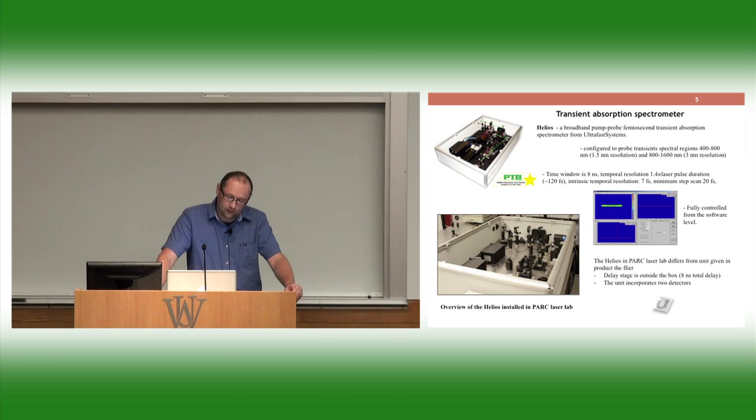If you'd like to measure some processes that take in time scale like 20, 50, 100 femtoseconds, it would be impossible to resolve from another component. It would be just buried under the instrument response function. However, the intrinsic temporal resolution is very good. If we do some upgrade in the future and we have like 15-20 femtosecond laser, that is quite possible. I believe it is possible to go down with the resolution to what is possible to reach, seven femtoseconds. It works in step scanning, you can manipulate this from the software level. The smallest step you can reach is 20 femtoseconds. That's like a snapshot of how it looks, it's not really complicated, very fine to use.